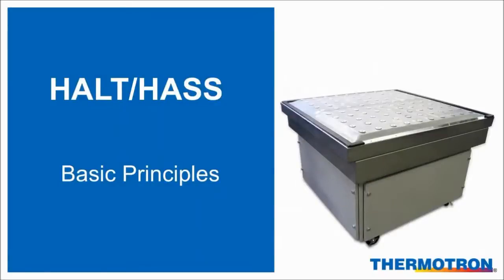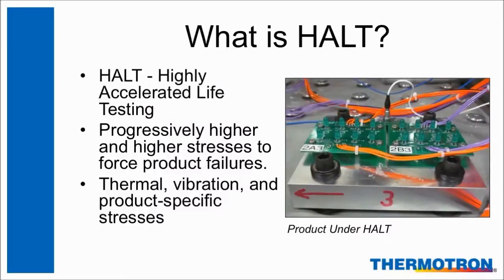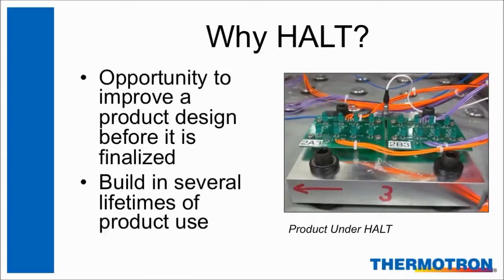Now I would like to hand it over to Mike Hicks, Thermotron Applications Engineer. He will be going over the basic principles of HALT and HASS. Highly Accelerated Life Testing, or HALT, is a test that uses progressively higher and higher stresses to determine potential product design weaknesses. Thermal, vibration, and product specific stresses such as voltage margining or humidity are used in HALT. The stress levels are typically increased significantly beyond the product specification and normal field stresses until it fails. The purpose of HALT is to quickly induce and detect as many failure modes as possible, expose the weakest points of the design, learn from the failure modes, and take corrective action. Failures found during HALT under high stresses are likely the same failures that will occur during a product's life cycle by much lower stresses over a long period of time. Ultimately, the idea is to build into the product several lifetimes of use in its field environment.